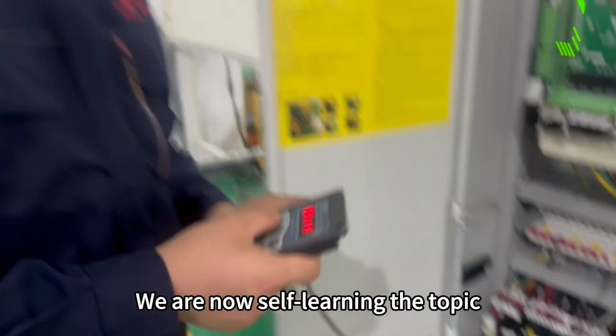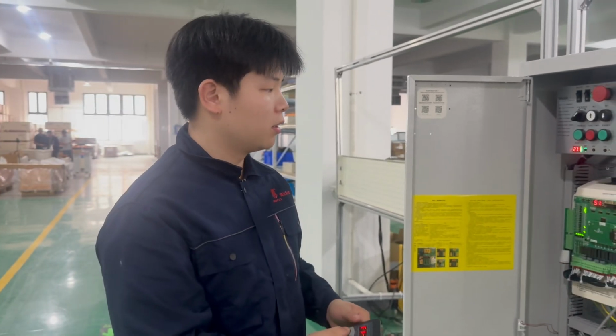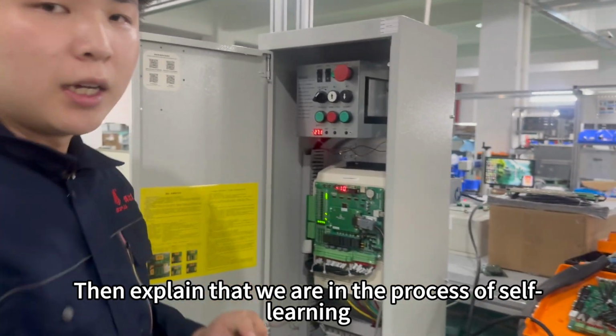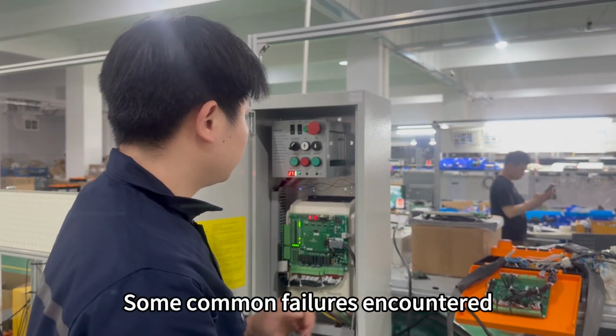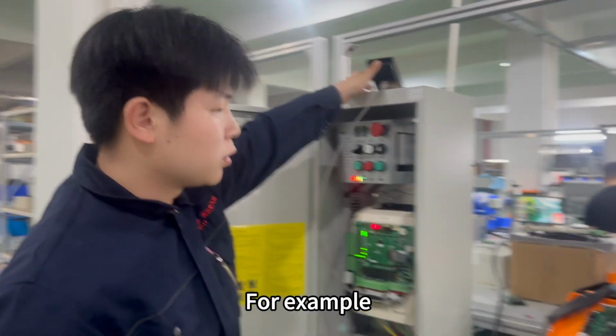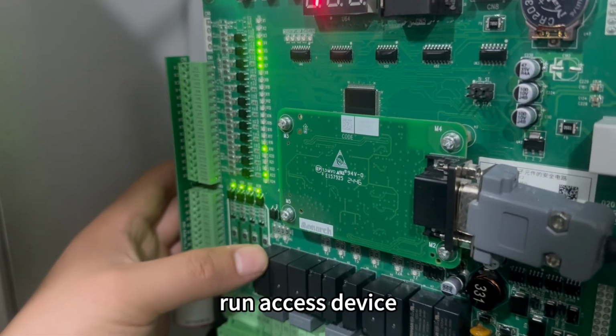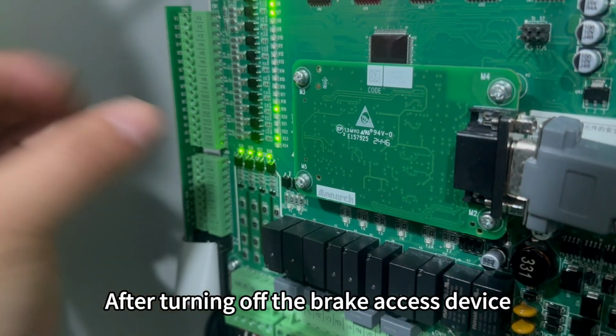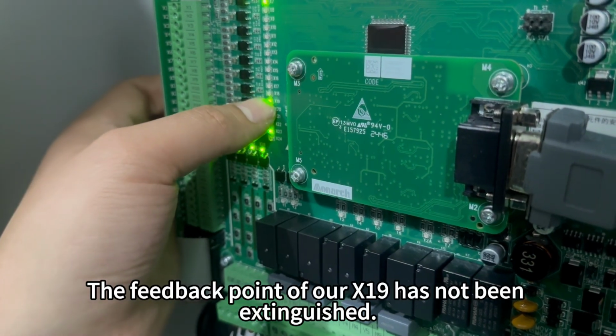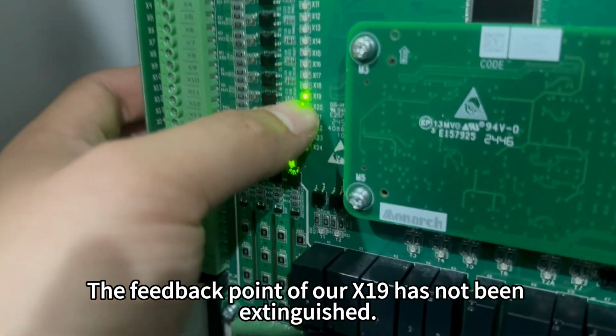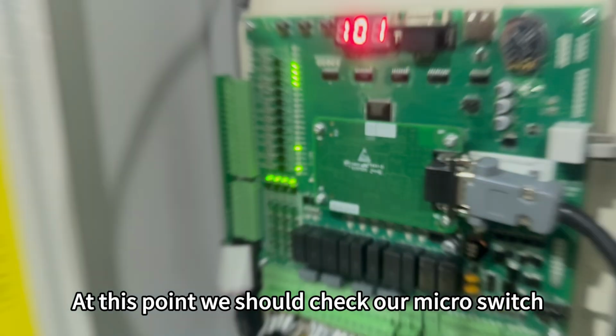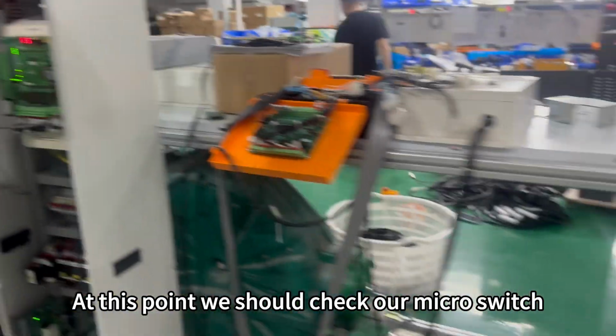We are now on the self-learning topic. Then I will explain some common failures encountered in the process of self-learning. For example, run access device. After turning off the brake access device, the feedback point of our X19 has not been extinguished. At this point, we should check our micro switch.